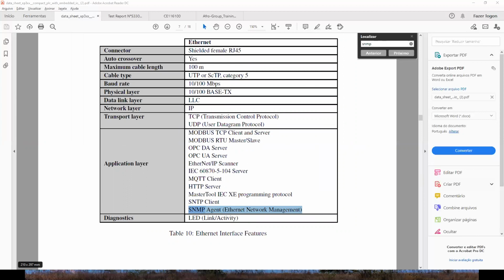Mauricio, while you check this information, maybe I try to add more information to Sandeep's question. As a general rule, the PLC is running tasks averaging from 2 to 5 milliseconds. The main task by default is going to be set to 5 milliseconds, but can go down to 1.6 to 2 milliseconds. The protocols usually run on different tasks as well. So usually a Modbus task or a serial port task would run as standard maybe 20 milliseconds, something like that. Of course, you can set everything.